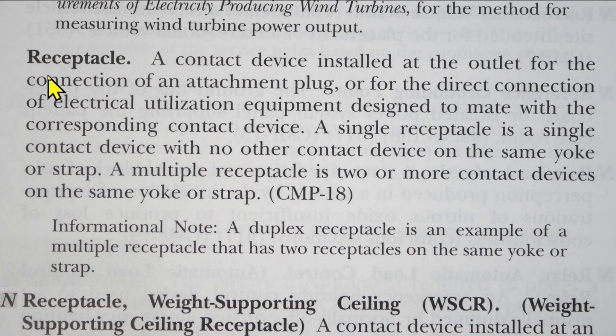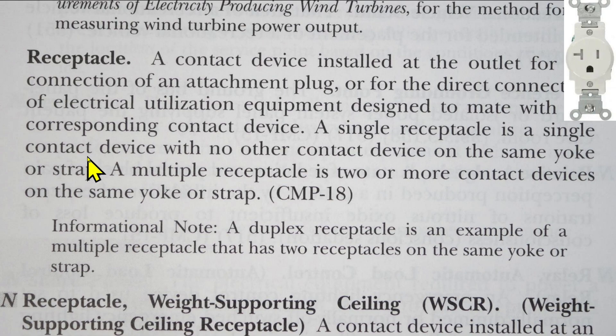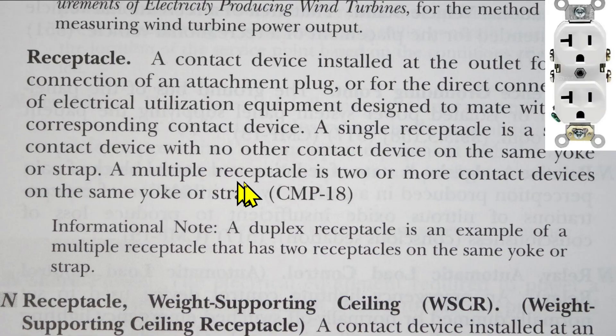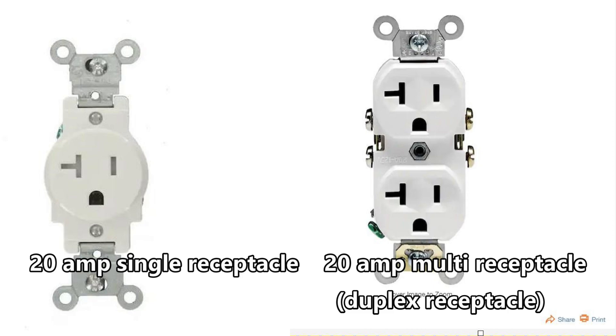Here's the definition of receptacle in the 2023 NEC: a contact device installed at the outlet for the connection of an attachment plug or for the direct connection of electrical utilization equipment designed to mate with the corresponding contact device. A single receptacle is a single contact device with no other contact device on the same yoke or strap. A multiple receptacle is two or more contact devices on the same yoke or strap.